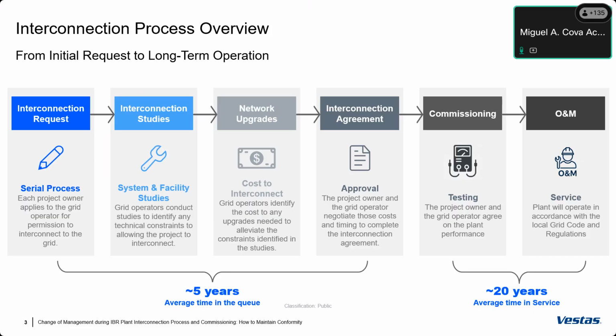Of course, it's not a secret that we have listed the UDM used for interconnection studies, but it's also crucial to enhance the commissioning of a plant. In the US today, Mod 26 and Mod 27 are two tests that are relatively easy to handle and pass, even with a generic model. But at Vestas we ensure we have a detailed internal commissioning process, making sure all frequency control works as expected, voltage control interactions, rise time, response time, etc., because those things will eventually come with the new IEEE 2800.2 and will surface more as more IBR connects to the grid. So it's important to have an internal protocol to ensure the commissioning is as expected.